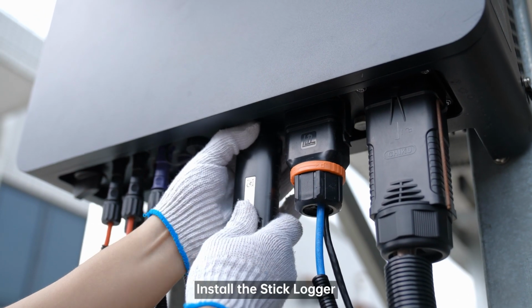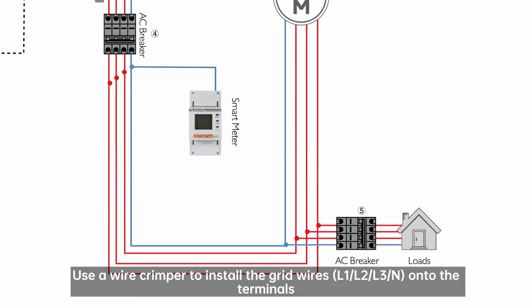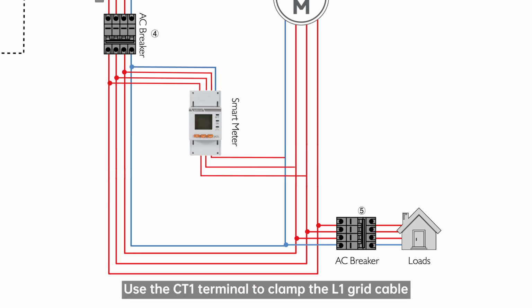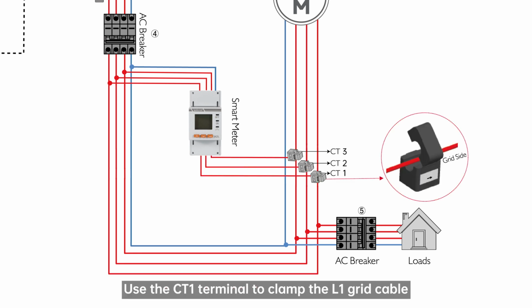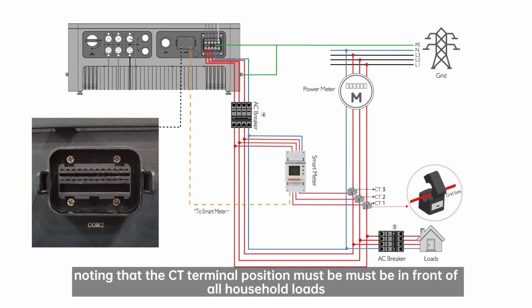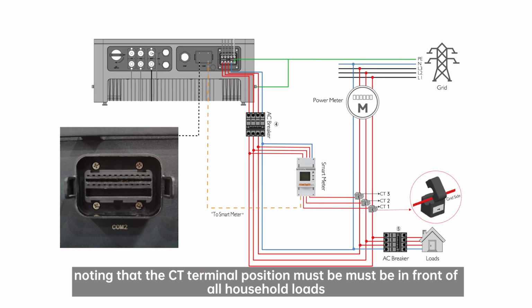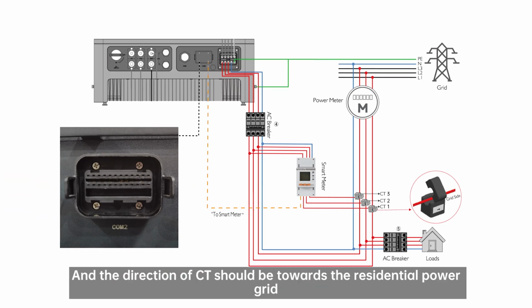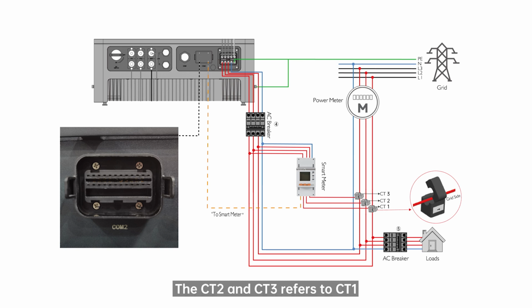Install the stick logger. Use a wire crimper to install the grid wires, L1, L2, L3, or N, onto the terminals. Use the CT1 terminal to clamp the L1 grid cable, noting that the CT terminal position must be in front of all household loads, and the direction of CT should be towards the residential power grid. The CT2 and CT3 refers to CT1.